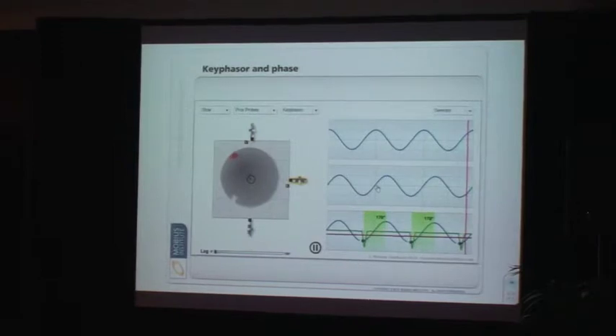Now that's true only if those two signals are the same amplitude and there's no other phase issues. As soon as we get into everything else, the actual signals are not the same. They're elliptical, they could be figure of eights if you compare them, and we don't see that 90 degrees phase relationship. But you'll see more of that in just a moment. Anyway, that's one of the ways we use this Keyphasor. We get this once per rev tach, and we can therefore get phase readings from that, and that's what we look at.